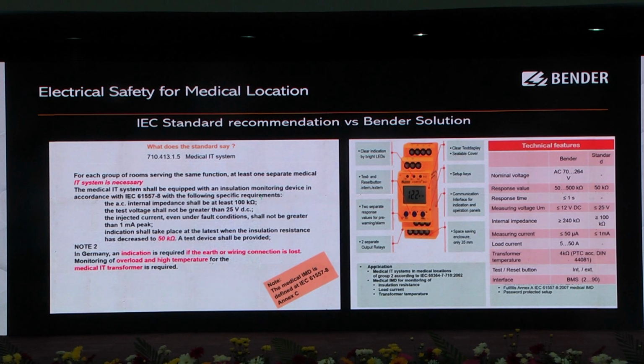So according to the IEC standard recommendation, here is the Bender solution. IEC says that for any IT system, according to 61557-8, an impedance of at least 100 kilo ohms is required for 230 volts. The voltage you inject for checking the insulation value shall not be greater than 25 volt DC. Again, less than 50 kilo ohms is the least resistance. Once your system goes below 50 kilo ohms, the insulation monitoring will give an alarm and inject a current pulse. That current pulse shall not be greater than 1 milliampere.